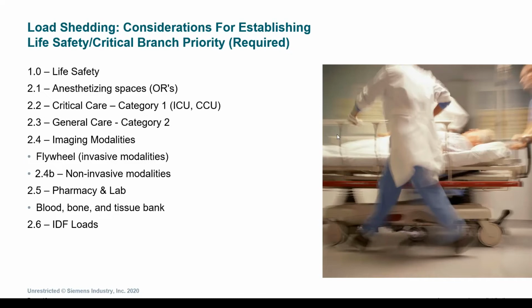And although those systems commonly have a UPS, whether it's a flywheel or battery, they only carry it from 10 seconds to a couple minutes. So it's important that those are still on that higher priority. From there, we look at the spaces and the systems serving non-patient spaces, but still critical to operation, such as the pharmacy, the lab, the blood, bone, and tissue bank, followed finally by the IDF rooms, if they're separated. Again, this is proposed and should be examined as part of each project, but does provide a guideline and recommendation.